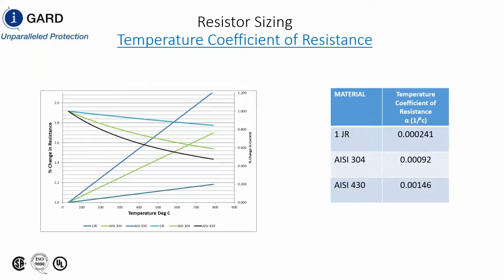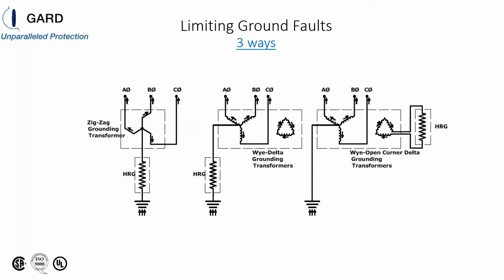And C57.32 suggests that the resistance not increase by more than 67%. And there's an IEC standard that's being developed, in which they've abandoned all resistance change because more or less it's just manufacturers in there. So there's 3 ways. I've been focusing on the zigzag transformer, but there's 2 other methods for limiting the fault current on the bus. You can use a Y-grounded delta configuration or a Y-grounded open corner delta configuration.